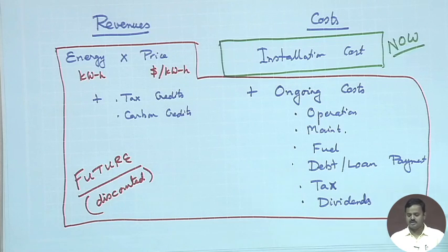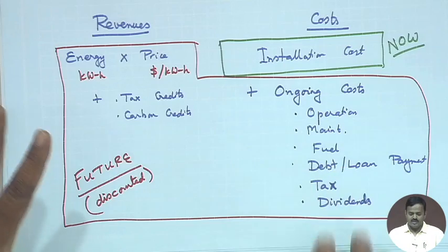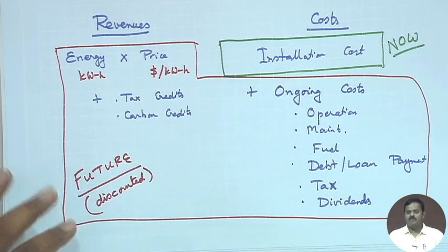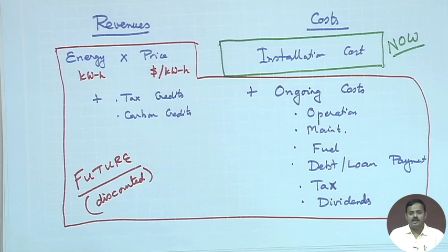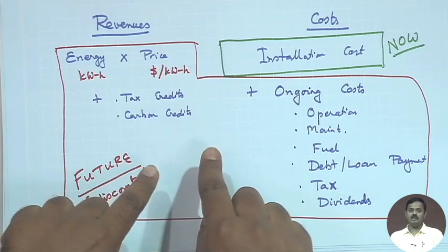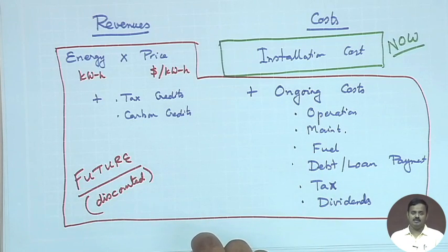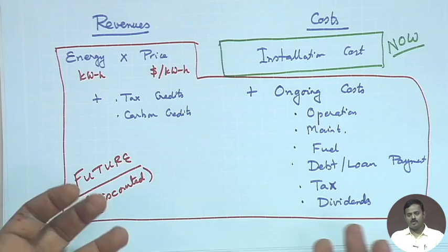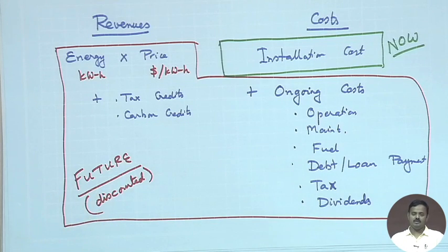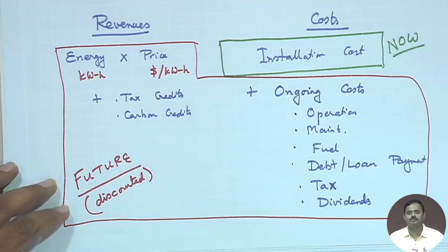You have to find the net present value by using the discount rate, right. So, the way I am showing this is again to drive home the point that all these can become part of your LCOE calculations. Okay. So, when we are comparing two installations, we have to make sure that the factors that have been incorporated while calculating LCOE must be the same for two LCOEs to be compared, okay, for the two installations.